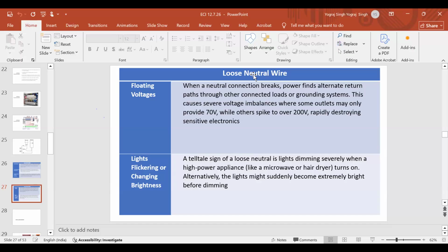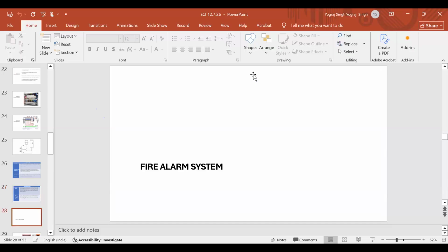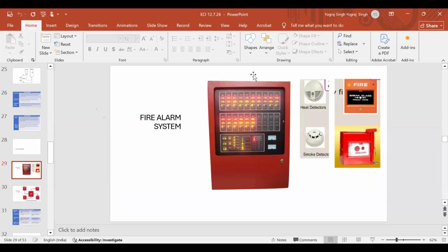Now, fire alarm system. What is a fire alarm? Fire alarm system, as you might have seen in any building, doesn't fight with fire, but it tells you there is fire. So there will be heat detectors, there will be smoke detectors. These break glass in case of fire. These press switches you must have seen elsewhere. Now this fire alarm system is fed from a battery supply. So it is independent of your normal power supply which is there in the building. So it has to be fed from a battery, independent battery.